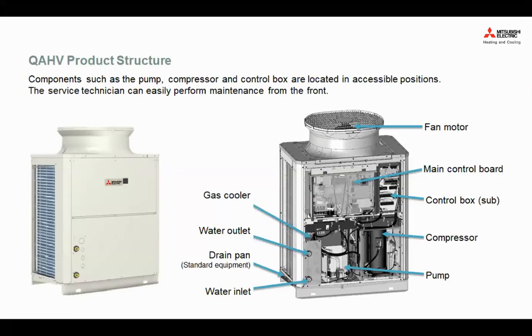Furthermore, here's a cutaway view for the product structure. Components such as pumps, compressor, control box can all be accessed on one side. So you are able to open the panel and then access the water inlet and outlet, drain pan, pumps, compressor, control box, and all of that can be serviced on one side. The unit does come with an internal built-in pump that can regulate the water flow based on the requirement. For example, what's the heating load required on the other side to heat up hot water, and also to heat up cold water. And then also what is the capacity requirement at that temperature, right? The fan, the compressor and the pump can ramp up and down depending on what is required based on your configuration and installation.